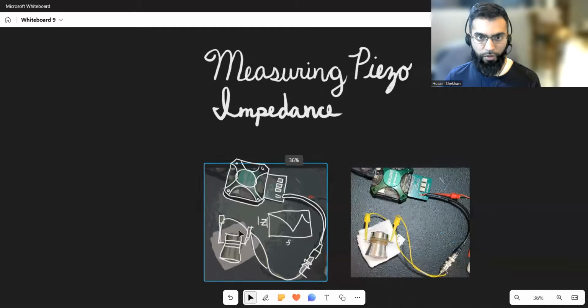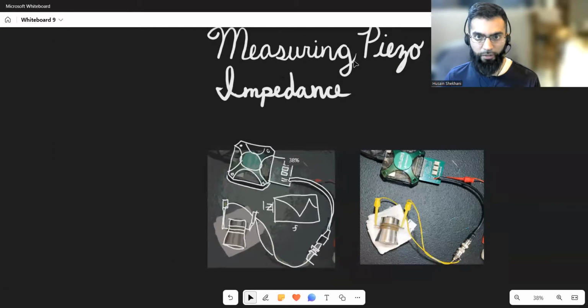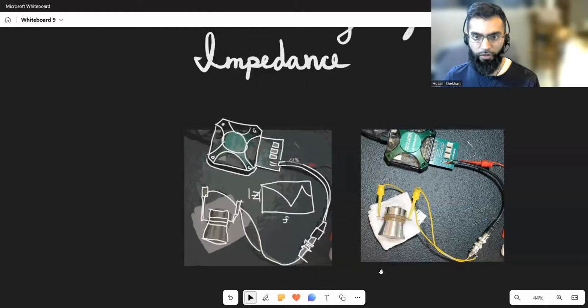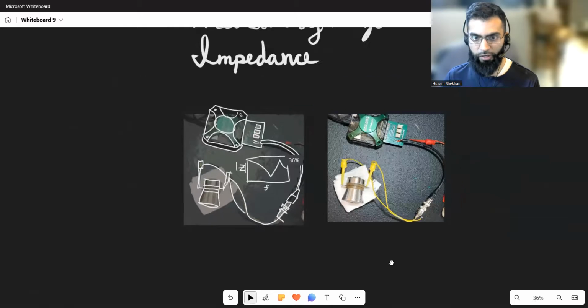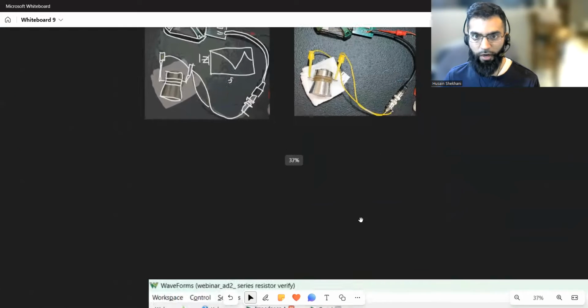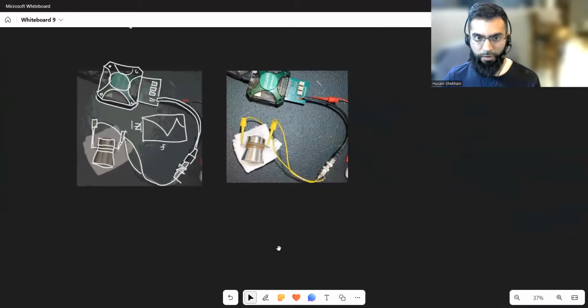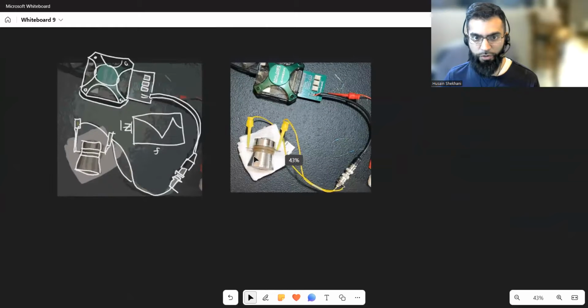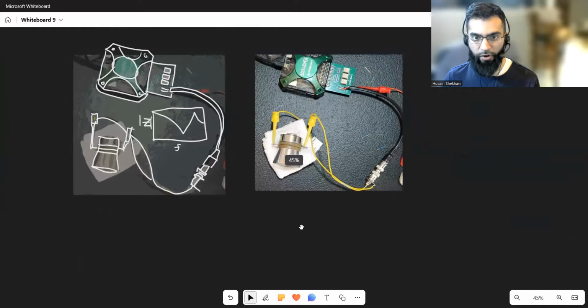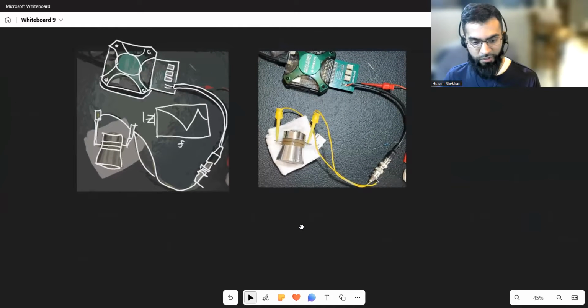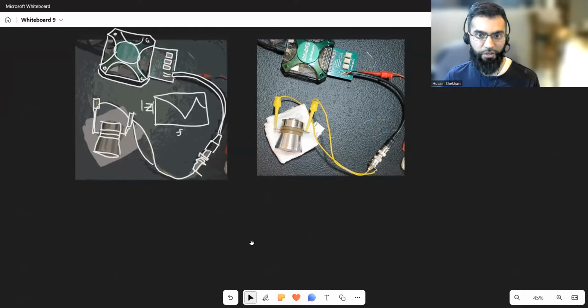Let's talk about measuring the piezo impedance. Here I have the piezoelectric device hooked up, an ultrasonic cleaning 40 kilohertz transducer. I also want to mention, especially for mounted transducers, they're high in anti-resonance impedance and low in resonance impedance, so they're very easy to measure. You don't have to pay much consideration at all for accuracy.